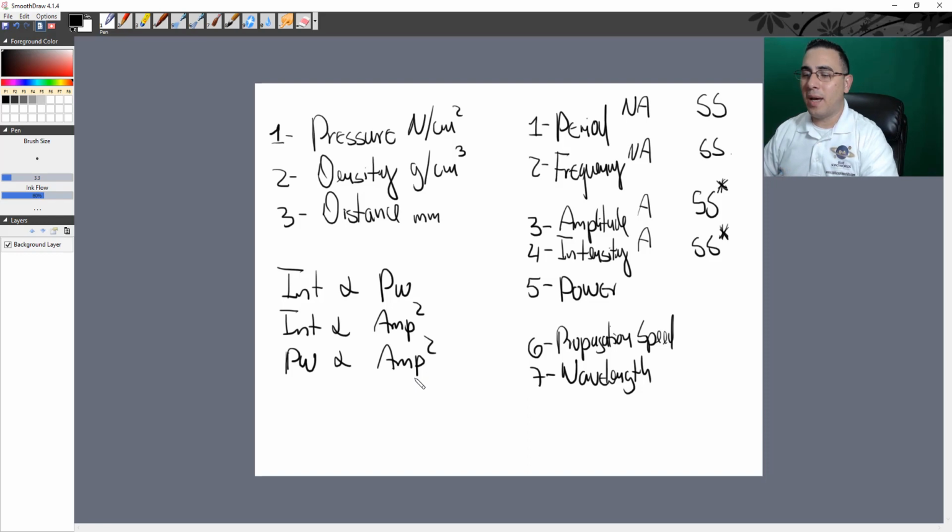And the one that we paid attention to was the SPTA, because we have this limit for these intensities that says the following: there are no confirmed harmful bioeffects over intensities that are 100 milliwatts per centimeter squared SPTA if the sound beam is unfocused, and if it is focused, then that number is going to be 1,000 milliwatts per centimeter squared SPTA.